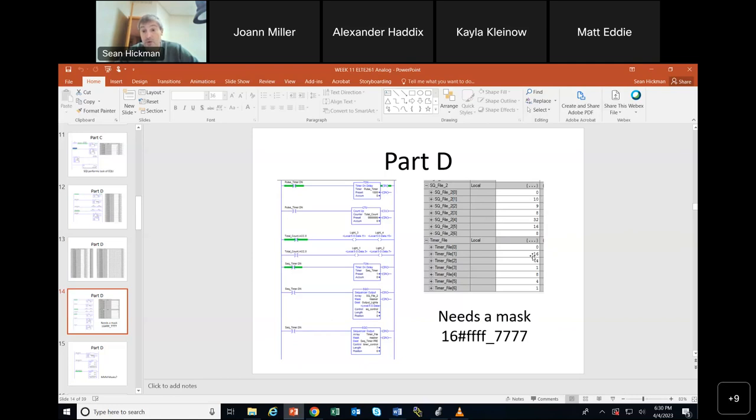Well, you had a timer, and instead of hitting the 10 16 times, you use that 16 for the timer preset. And then when that got done, you notice the sequence timer done here, it advances the output module because we want a different number in the output module, just like you did here, except we just used it a million times. It advances the number sent to the output module, but it then just sequences the timer preset. So the timer goes from a 16-second timer to a 4-second timer, and therefore it keeps 9 in there for 4 seconds. Boom, the timer hits done.